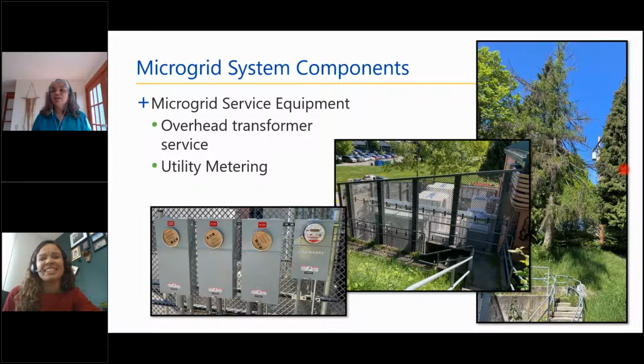And then you see the utility metering. You'll notice 1 meter is in, with covers right now for the other 2 meters. We chose to include the devices in the microgrid into our AMI system, and those meters, I'm not sure if they're installed yet, but the intent is to install them before the system energizes. So not only will we tell what the connection from the customer meter looks like to the grid, but we'll be able to include the battery and the solar in our analysis and in the AMI data.